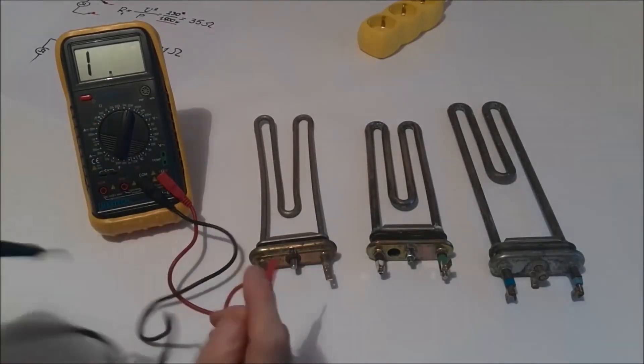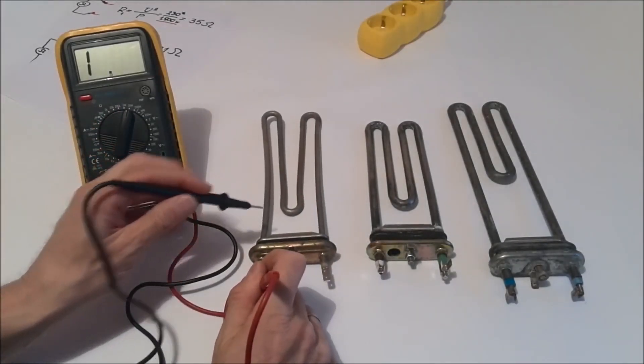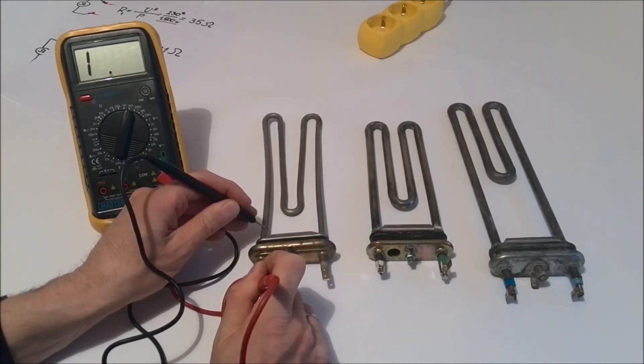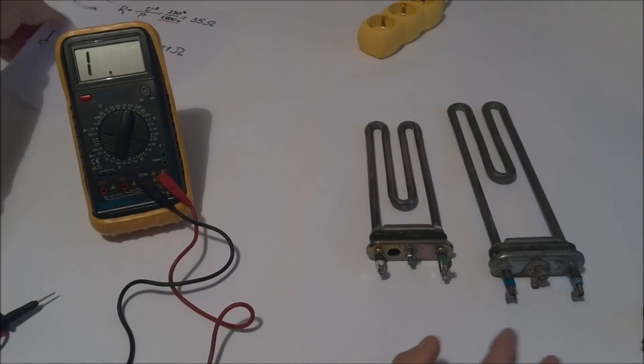We moved the range to be much higher resistance and tested the heater again. We still see that the resistance is infinite so this heater is not functional. Let's get back to the scheme again.